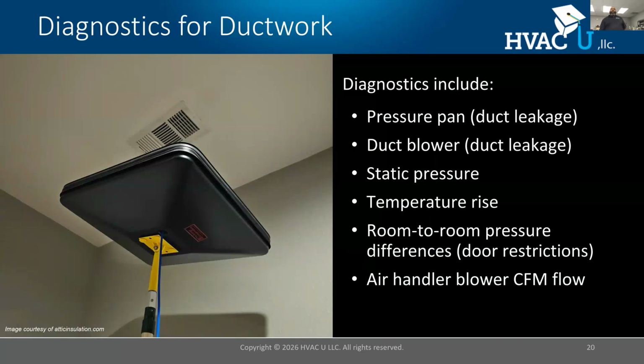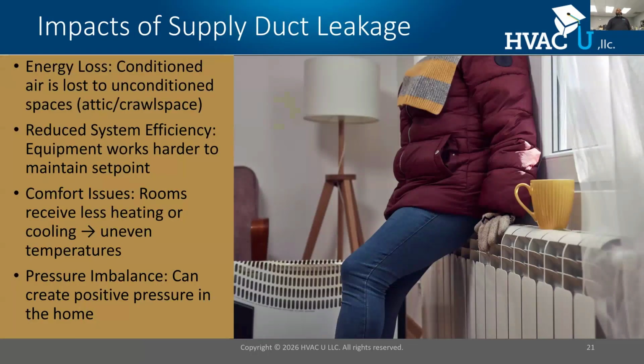All right. When we go to talk about those issues, these are the solutions that we're going to use to find the problems. So in order to find the problems that we just mentioned, we're going to talk about these diagnostic tests. So we have a pressure pan, a duct blower test or duct leakage tester, static pressure, temperature rise, room to room pressure differentials, and then measuring air handler flow. All right. So these are the 6 tests that you can use day in and day out to solve any kind of duct problem. It's going to get you right into what's going on with that duct system.